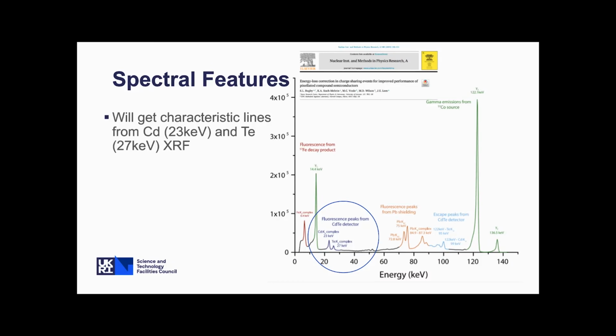They're actually coming from the main peak, so you also end up with some escape peaks here. Whenever you have a large peak above 30 keV, at 23 and 27 keV below that peak, you'll end up with some escape peaks from the cadmium tellurium itself.